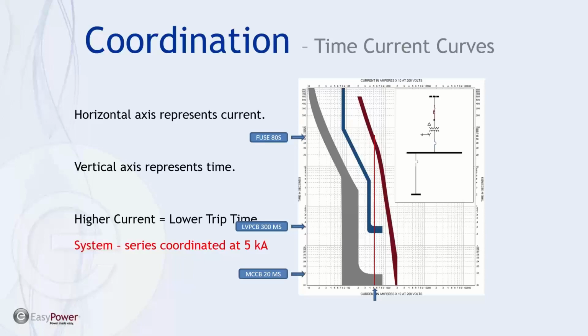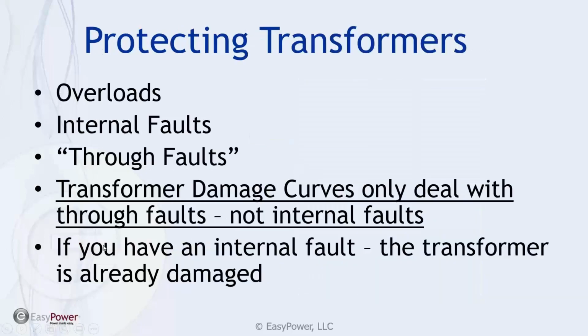Now, what we're going to focus on is protecting specific elements. Transformers are usually the most expensive element in a system, and they need to be protected from overloads, from internal faults, and through faults. The transformer damage curves only deal with through faults, not internal faults. And basically, if you have an internal fault, the equipment's already damaged. There's already a short or an open in the transformer, and then the TCC itself is not particularly useful.